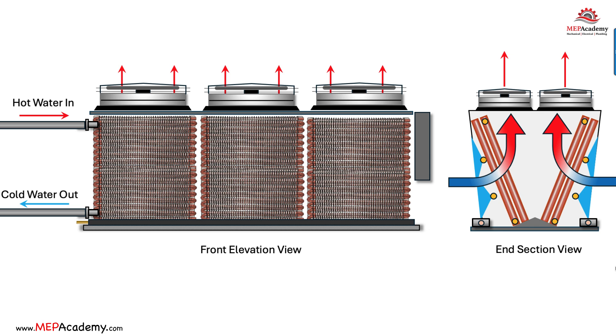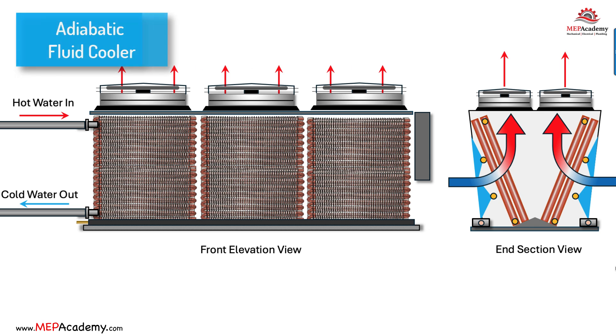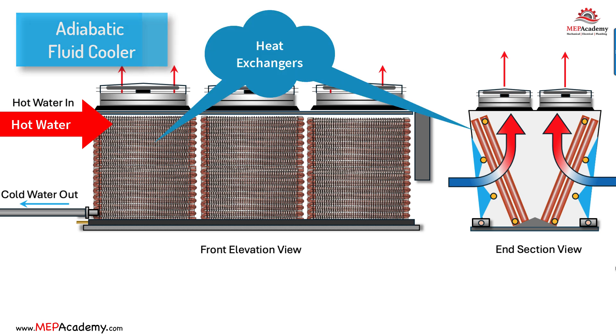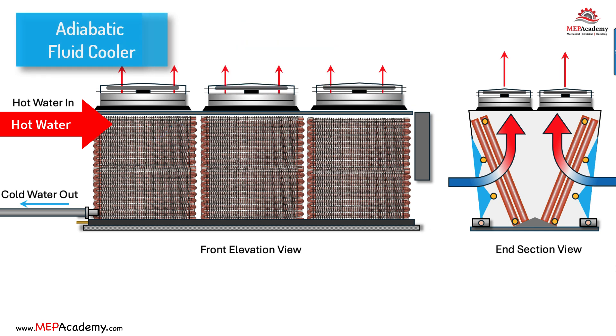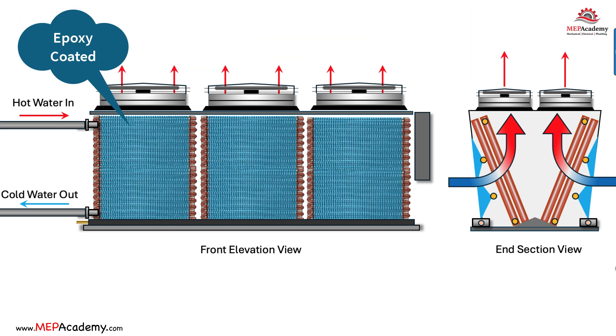Here is how the adiabatic fluid cooler works. The hot water flows into the heat exchanger, which consists of coils of tubes surrounded by fins. As the hot water flows through the tubes, heat is transferred to the coil surface and fins of the heat exchanger. The heat exchanger can be provided with an epoxy coating to increase corrosion resistance without sacrificing unit capacity.